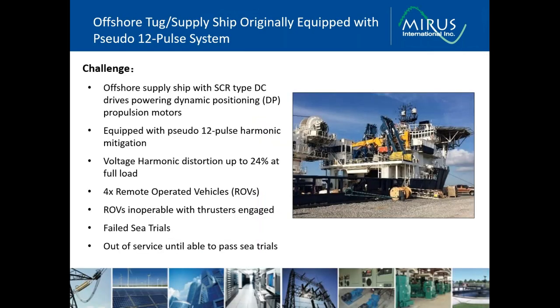And the fourth example here was an attempted use of phase shifting on thyristor bridge in an offshore service vessel. This vessel was equipped with DC propulsion drives and was purchased with the intent of upgrading with additional equipment such as remote operated vehicles and cranes, additional cranes, to service the offshore oil and gas industry. However, due to multiple failures caused by the harmonic voltage distortion, it could not pass sea trials.